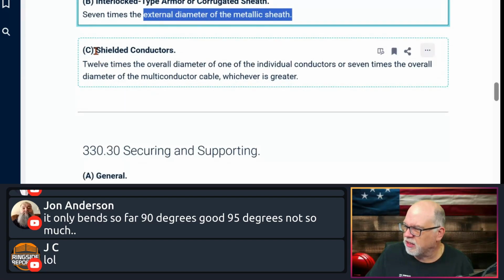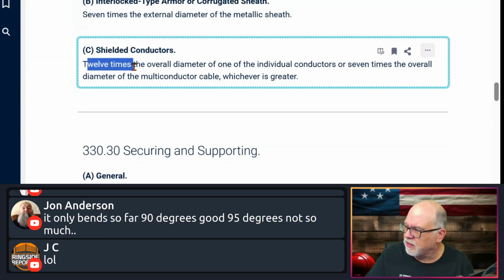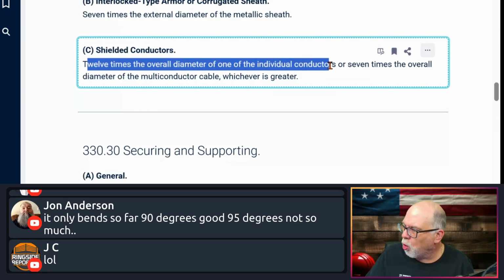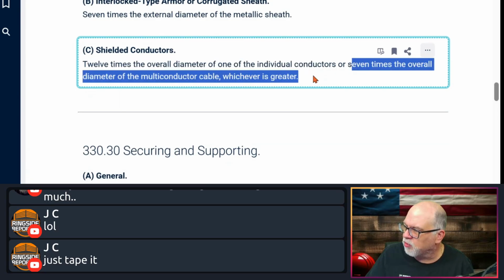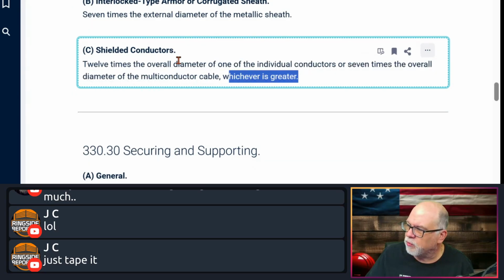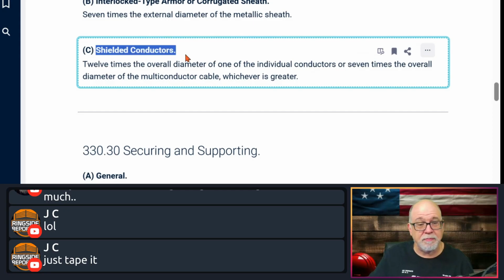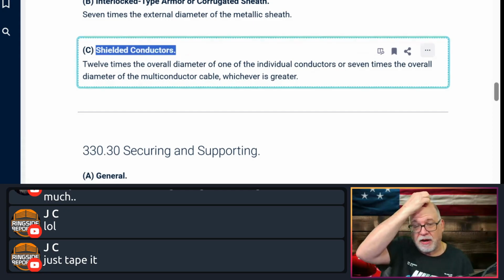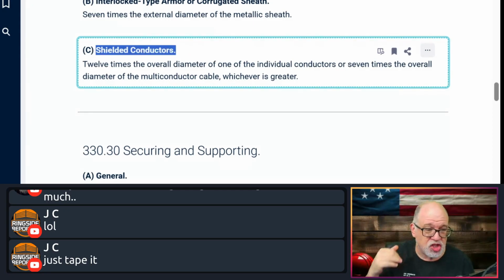All right, shielded conductors. It's 12 times the overall diameter of one of the individual conductors, or 7 times the overall diameter of the multi-conductor cable, whichever is greater. That is when you have shielding, maybe like a polymeric aluminum shielding or whatever, inside of the actual MC. Then that's what this would be an example of, a shielded type.